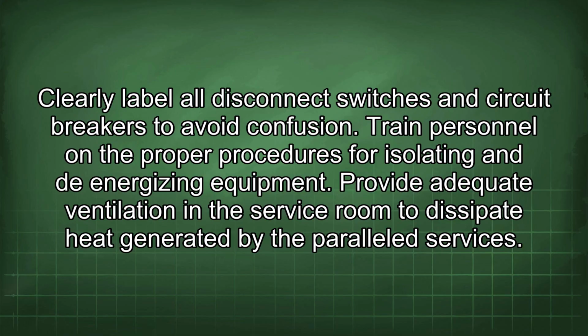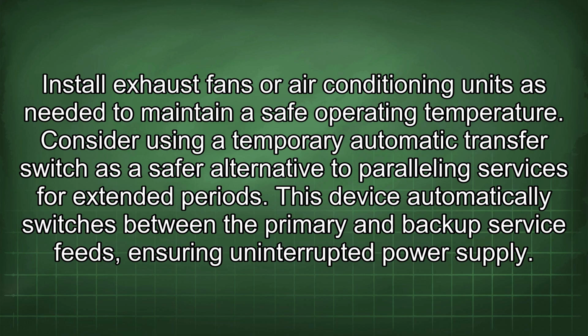Provide adequate ventilation in the service room to dissipate heat generated by the paralleled services. Install exhaust fans or air conditioning units as needed to maintain a safe operating temperature.